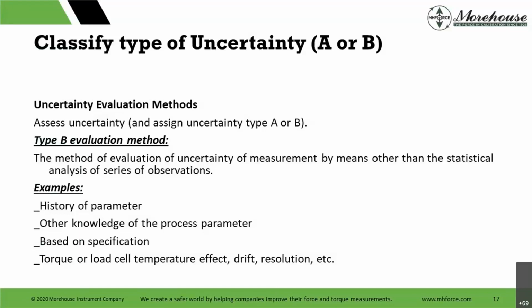Hey, if you're operating at a temperature, our lab is calibrating at 23 plus or minus 1 degree. So you might get a cert from us that says 22.6. If you're operating at a temperature that's, say, 25 degrees, you need to put that in the budget. Like I said, the little things add up. If you're operating at 25 versus 22.6, now your budget might be, hey, how much do I vary from that temperature spec? In my lab, I'm controlling within 0.1. Maybe I'm just going to use 1 degree, because the worst case I can see is me varying to 23.6 degrees, the highest temperature I'm going to see in my lab. You still need to put it in. It's just a lot smaller number.